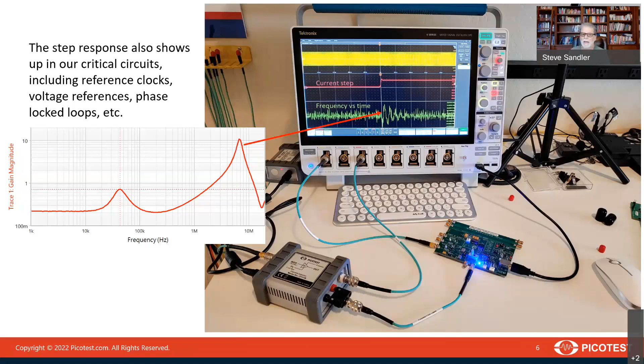That ringing is approximately 1 megahertz peak to peak, and that occurs at about 7 megahertz. And so the point of this really is that the impedance tells us a lot about a lot of different things. I said that it's an intermediary term for performance. And in this case, this would be phase noise or spurious responses. And so that 7 megahertz resonance interferes with the phase noise of the reference clock. And so one of the reasons that we want to measure the impedance is so we can look at things like how it interferes with that reference clock.